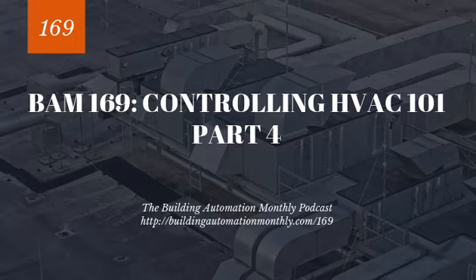Let's take a look at just a single hot water boiler. How are we going to control this simple machine? And I know simple is a relative term, but how are we going to control it? Well, when it comes to pretty much any boiler, we are going to need really three things: flow, fuel or power, and control. So flow is critical. Without flow, we can damage systems.